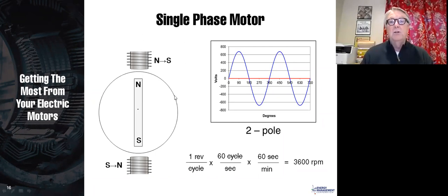Now, I just told you that you don't know which direction it's going to go, and it pulses. And you say, well, wait a minute, I've got lots of single-phase motors. They always go the right direction. And the reason for that is they have Band-Aids. I'm going to talk about Band-Aids in a minute, but because of the problems of the single-phase motor, you have to add something to get that thing to start correctly. And that could be several different types of technologies, and we will talk about some of those technologies in a moment.